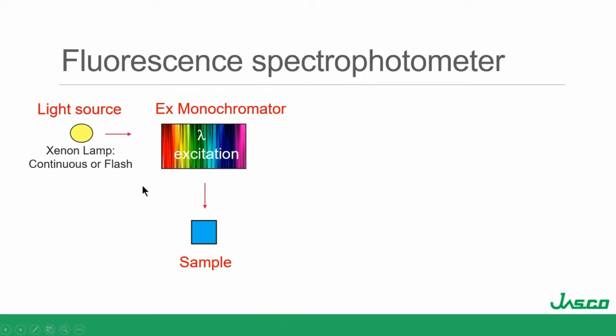Now I want to choose what wavelengths I send in to excite my sample. I could do that with a filter — there are filter-based systems that let a lot more light through, but then I don't have the flexibility of selecting wavelengths. A monochromator gives me easy wavelength selection and the ability to scan the excitation monochromator. If I were just doing a UV-Vis experiment, I'd want my detector on the other side — light in, light out — take a ratio and I've got absorbance.